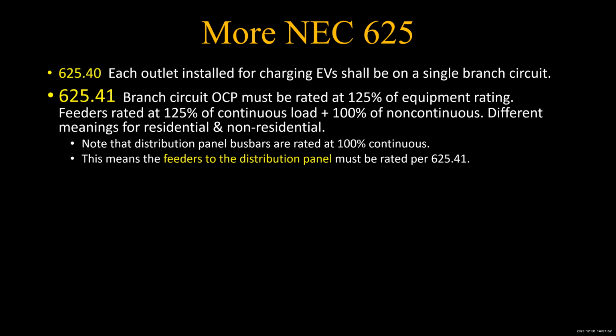that's another story. In any case, the way you size your branch circuit, let's say you got a distribution panel and you want to see if you got enough room to put in a level 2 charger, you start out with 100% of the non-continuous load. In other words, you got your Article 220 calculations for load calculations on a panel, and you'll come up with a non-continuous load, which might be, say, 110 amps.